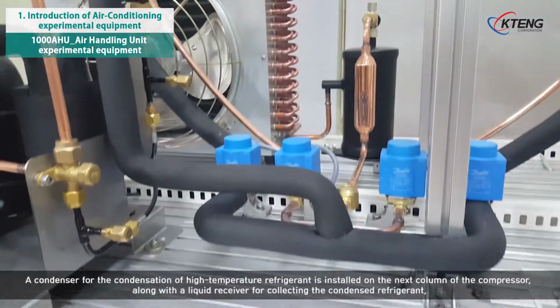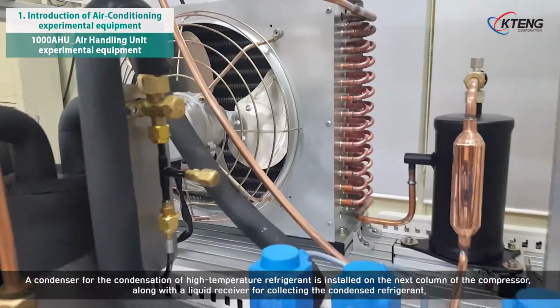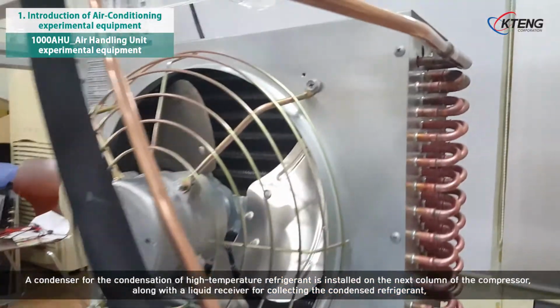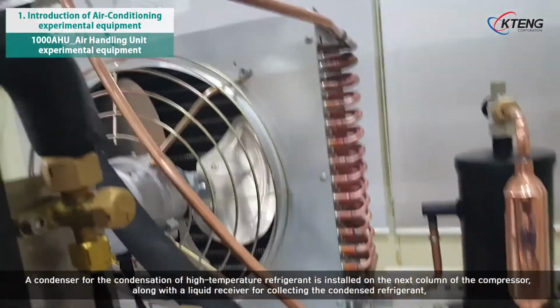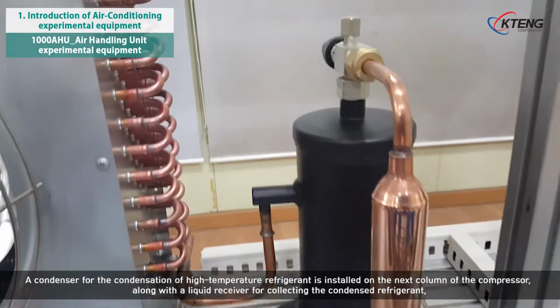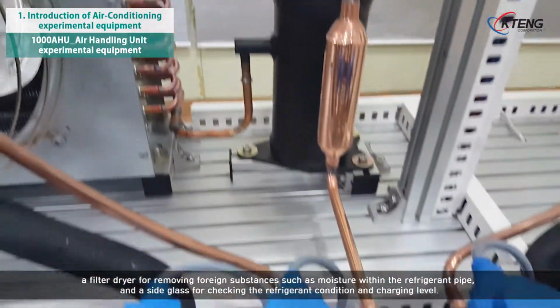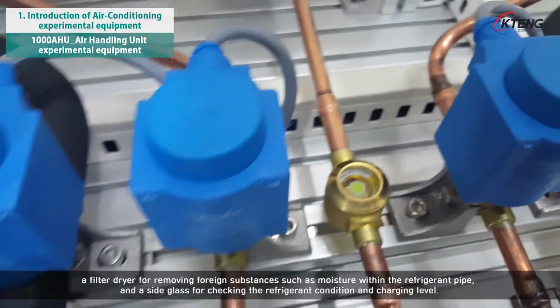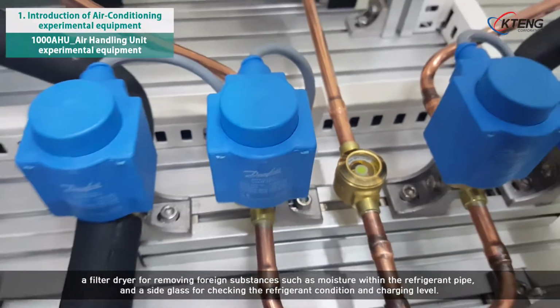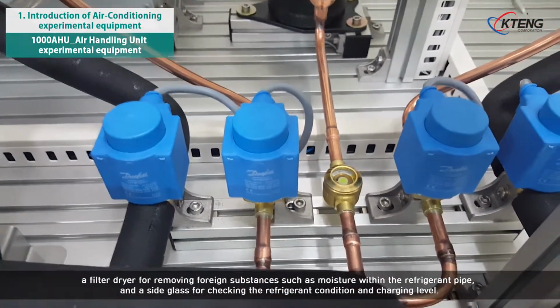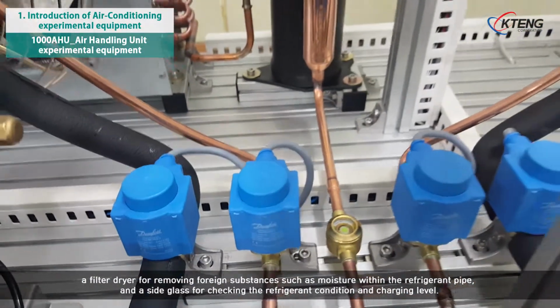A condenser for the condensation of high-temperature refrigerant is installed on the next column of the compressor, along with a liquid receiver for collecting the condensed refrigerant, a filter dryer for removing foreign substances such as moisture within the refrigerant pipe, and a sight glass for checking the refrigerant condition and charging level.